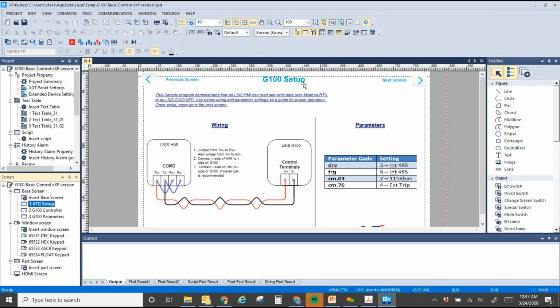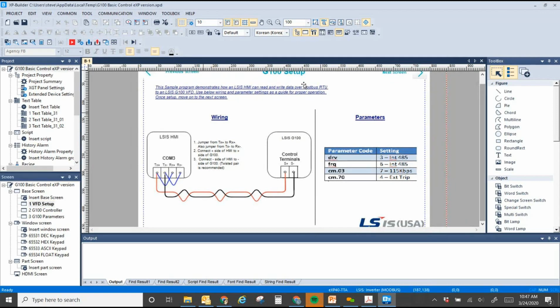This is a sample program that demonstrates how an LSIS HMI can read and write data over Modbus RTU. Someone asked if we can communicate directly to a drive and read and write parameters. That's exactly what this program does, and you could use either an EXP or an IXP HMI for it.